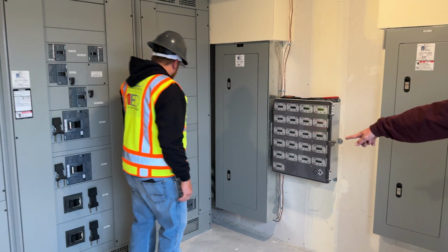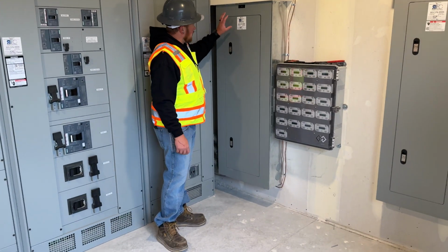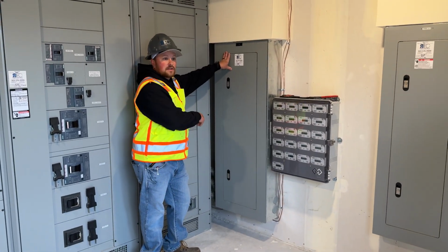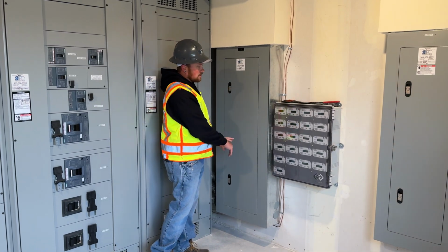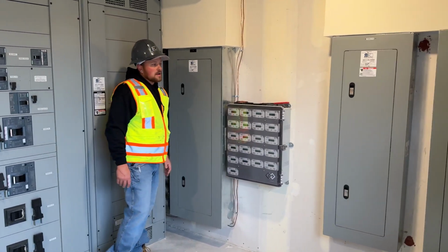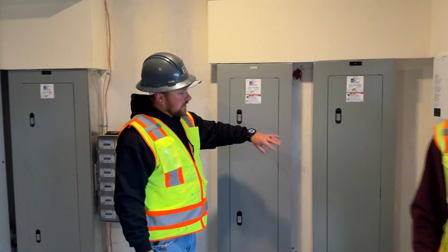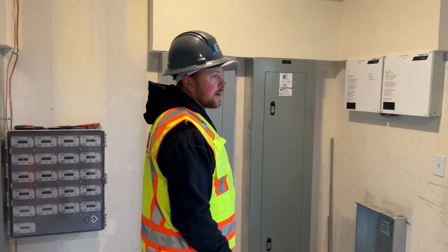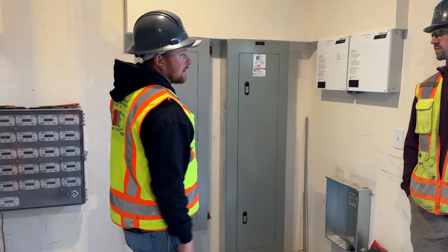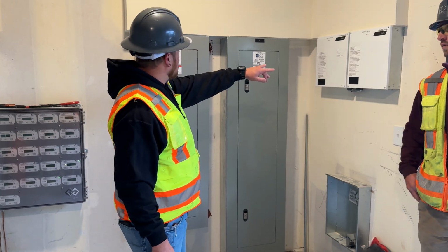Yeah, there's a H1 breaker. Yep. This is the P1 panel that feeds all the units down on this floor. Again, there's a panel schedule in here. Here's our sub-metering.